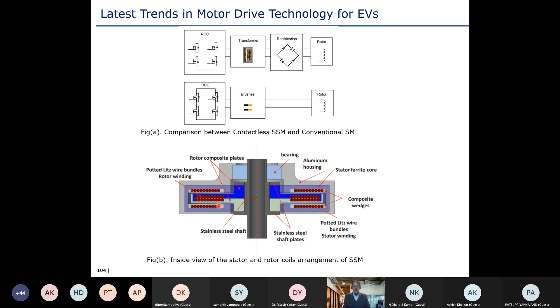This is your shaft, and this is the rotor. So this rotor moves, and this is the stator part. So you move in, and then there is always a direct link between the stator high frequency supply and rotor induced current. Here you see there are two inverters, one main inverter, and another is the rotor current controller. So you feed this motor with three-phase supply and with the rotor current controller.